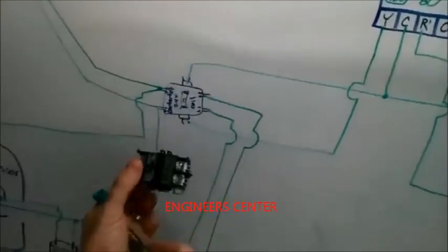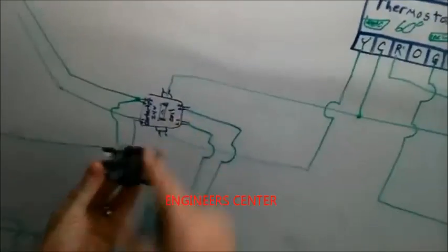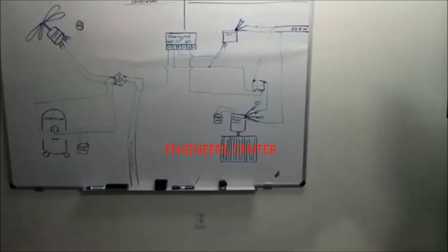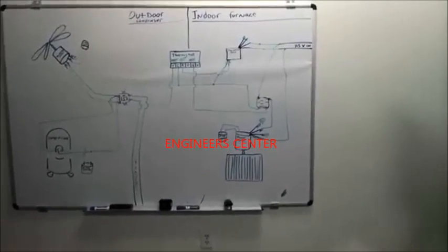You know a contactor needs 24 volts to close. Give it to it. How are you going to give it to it? It's from the transformer. Now, don't get caught up if it's going through a board or through some time delay, because essentially that's where it's going, and that's what that needs to turn on. So that's a real basic understanding of an electrical system in an air conditioner, how it works.